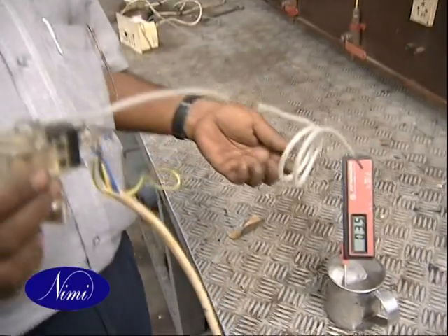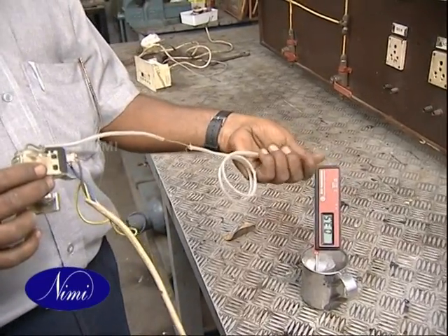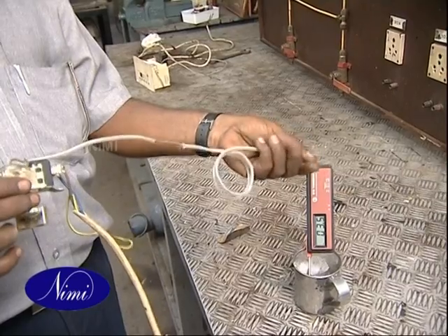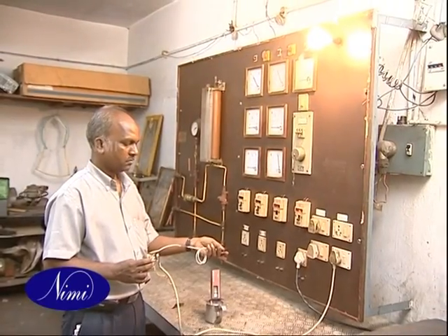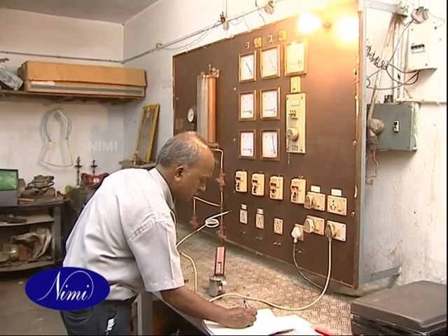Quickly take the reading of the thermometer. Remove the thermal bulb from the ice cubes. Hold the thermal bulb by hand and warm it until the thermostat goes to cut in position, which will be indicated by the glowing of the bulb. Repeat the steps for 3 readings and note the temperatures carefully and record in a table.